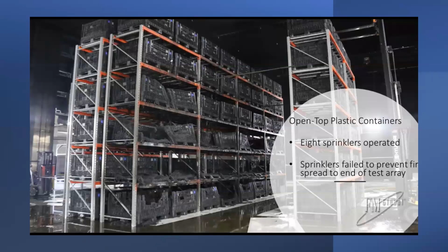By the end of the test, a total of 8 sprinklers operated and the fire burned to both ends of the rack. If the rack was longer, the fire would have continued horizontally, resulting in more ceiling sprinkler operations until the water supply would be overtaxed. So here we had a similar product consisting of an uncartoned, unexpanded plastic, but the sprinkler protection design that was used in the standard uncartoned, unexpanded plastic commodity test failed to stop the spread of fire within the rack. The difference in this test was that the sprinkler water was being collected in the combustible open-top containers and was not allowed to flow to the lower areas of the rack where the fire was located.